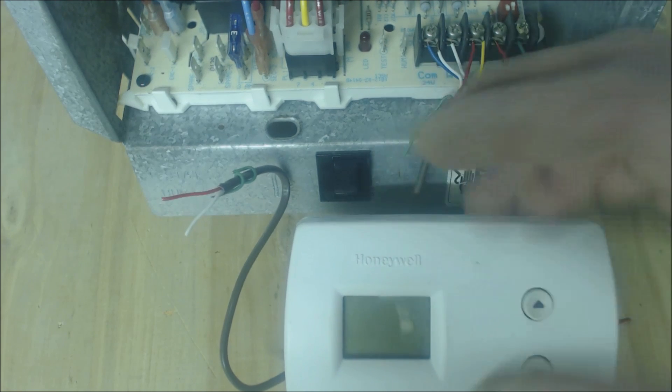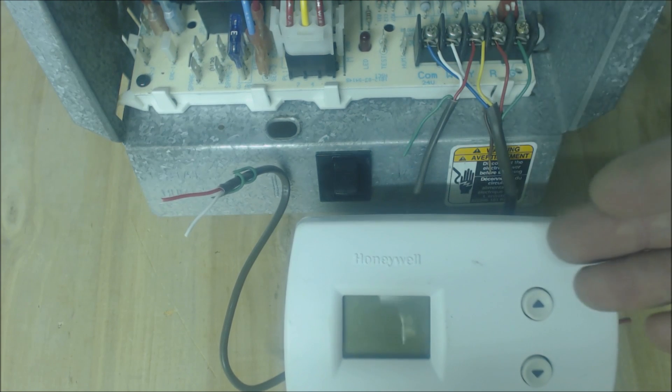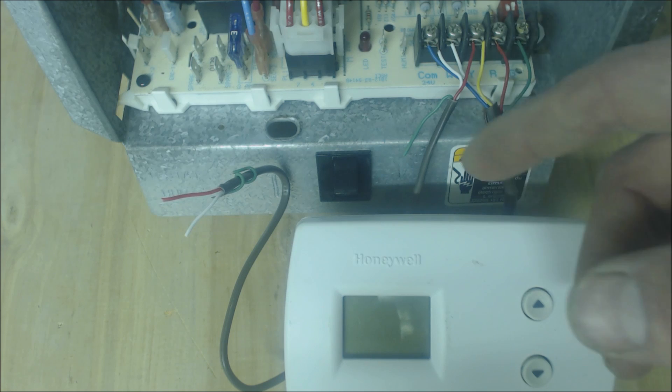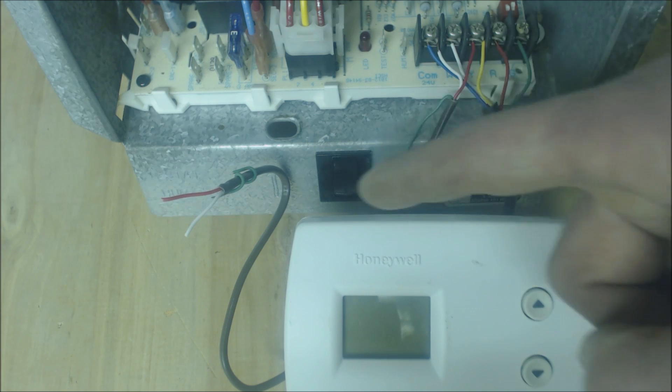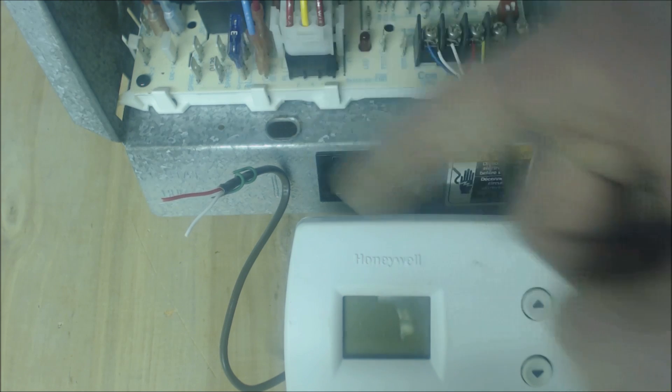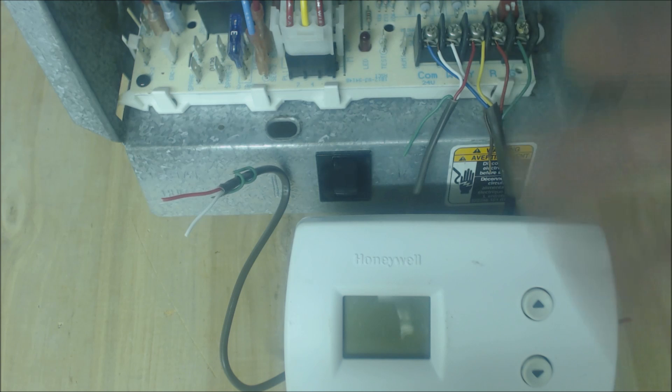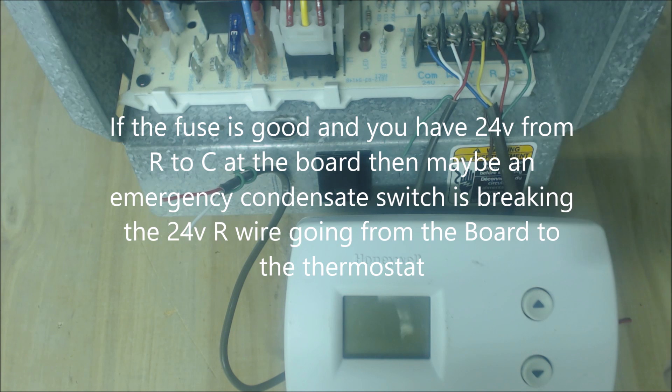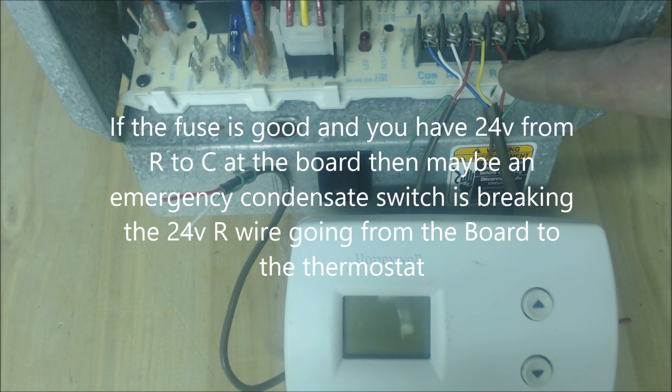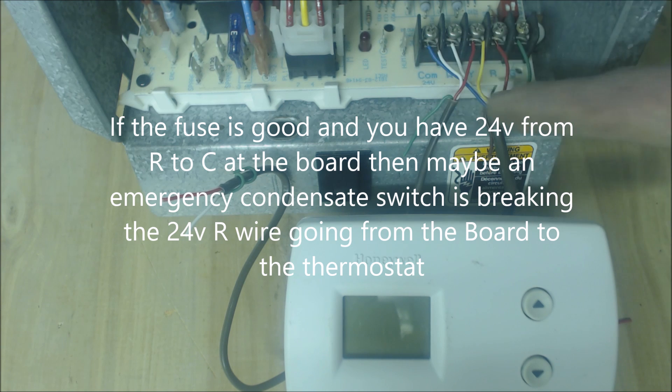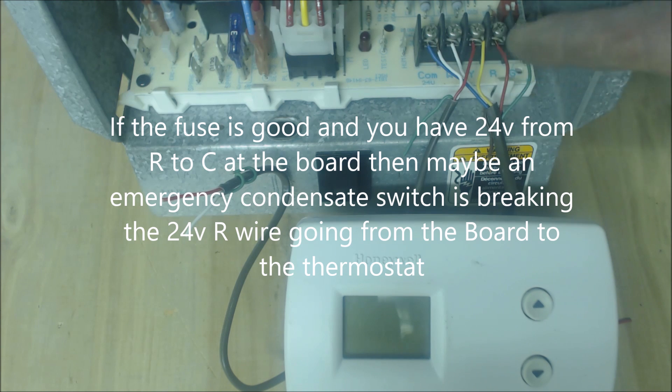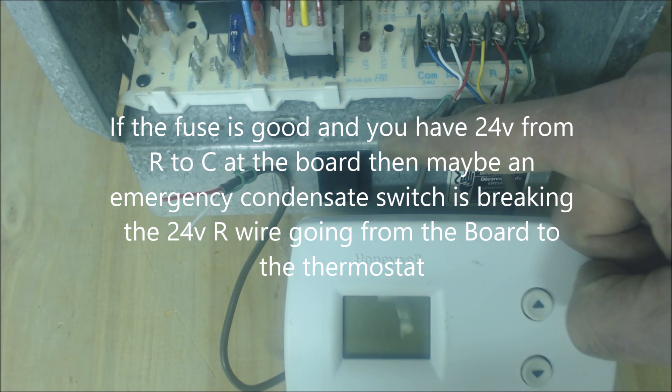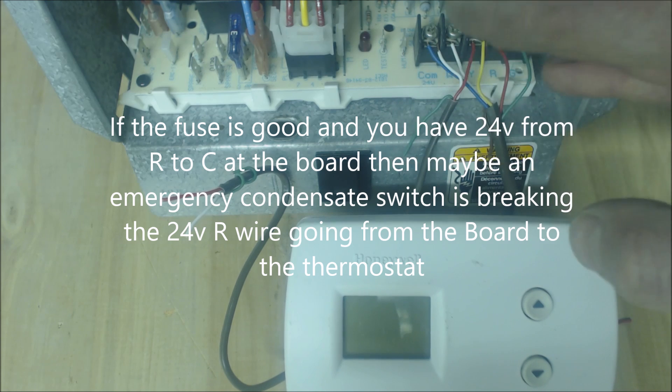If you're not able to turn your furnace or air handler on, there could be several reasons why. First thing is if you turn the power off and pull this fuse, if the fuse is bad, one of the things that it could be is that R 24 volt hot and C common are touching, or R and the ground are touching somewhere.